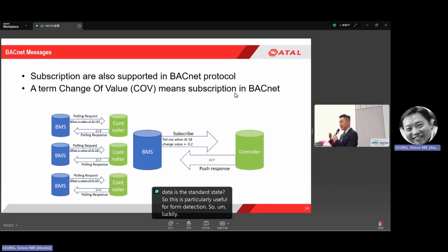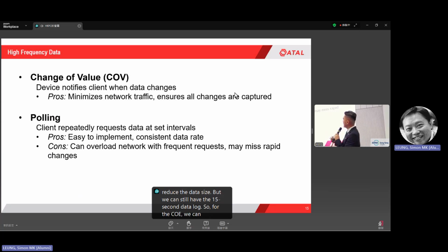So luckily, BACnet supports COV, change of value. That means we can have the data in a high frequency way. Let me give some examples. For the on-off status, for 1 day, maybe the chiller is only on 1 time and off 1 time. When we use change of value, that means for the whole day, we only have 2 data to represent the whole day. For the temperature, if the COV is 0.2 degrees Celsius, that means the data is only transmitted when the change of value is more than the threshold value. So by using the COV, we can significantly reduce the data size, but we can still have the 15-second data log. So with COV, we can minimize the network traffic and ensure all the changes are captured.